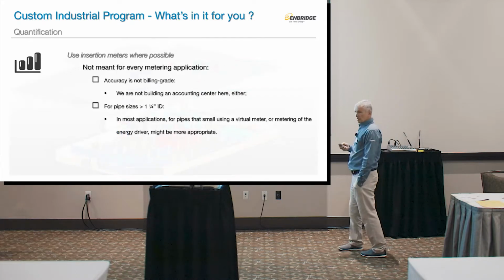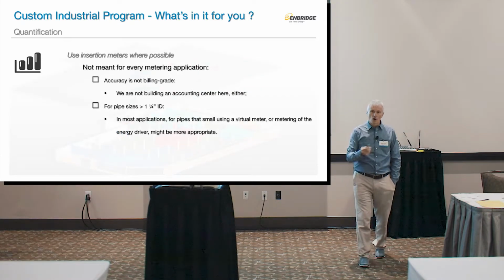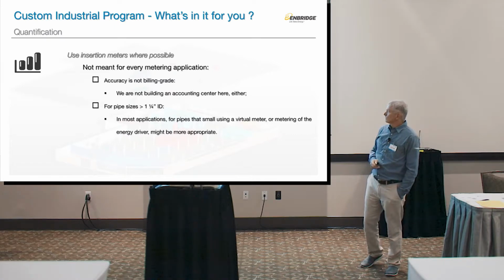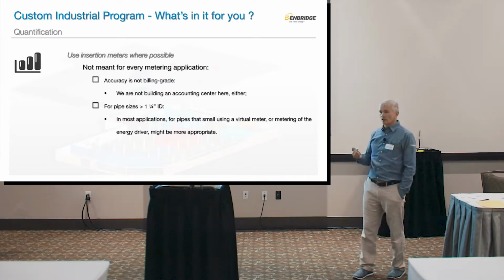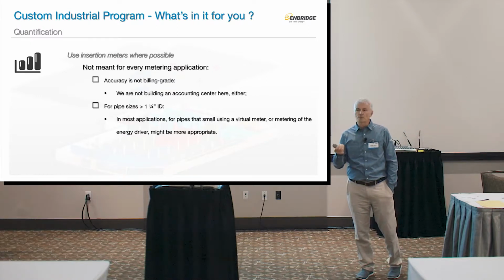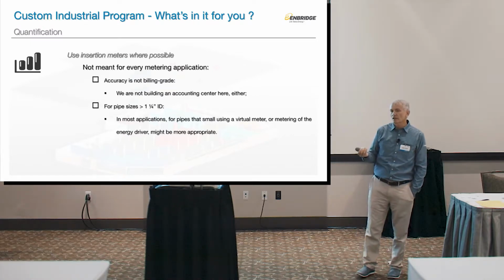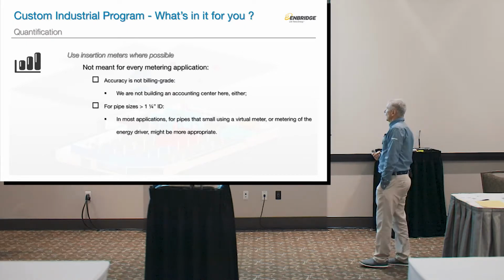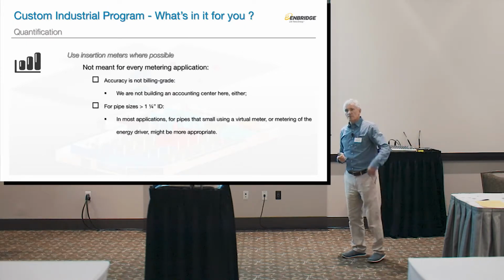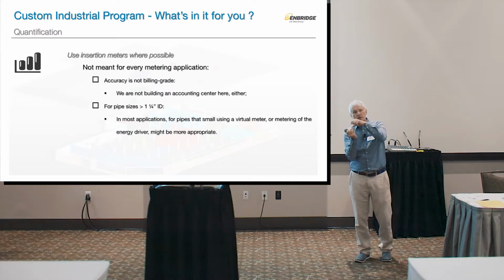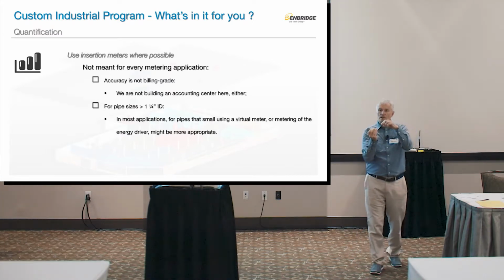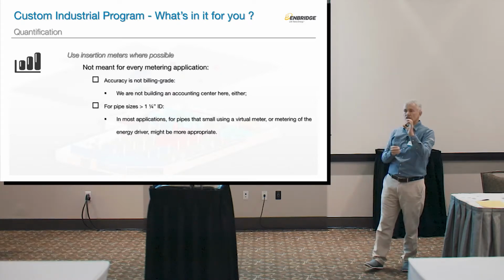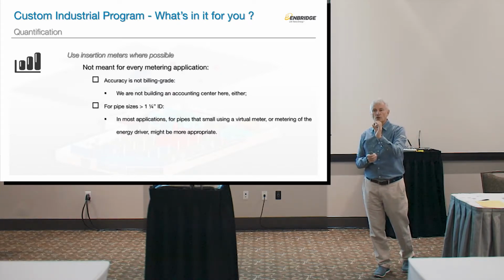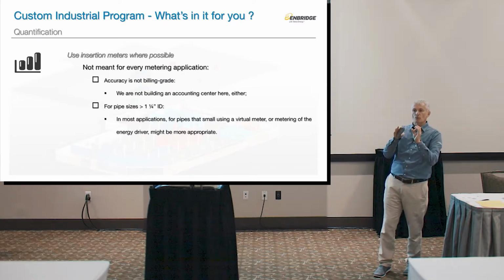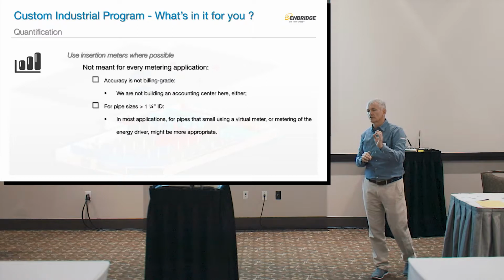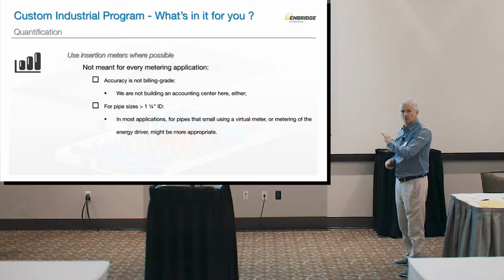It's not meant for every metering application. The big objection we hear is that it's not billing grade. True, but how many of your projects are really accounting center quality? Who are you going to bill for that? If you're plus or minus 5%, does that really matter? No. It's for pipe sizes over 1.25 ID because the tip goes into the pipe, so a smaller pipe would restrict the flow. But with a smaller pipe, the gas use is so small that I'd use a virtual meter or meter the driver instead. So for most cases, I'd use an insertion meter for quantification.